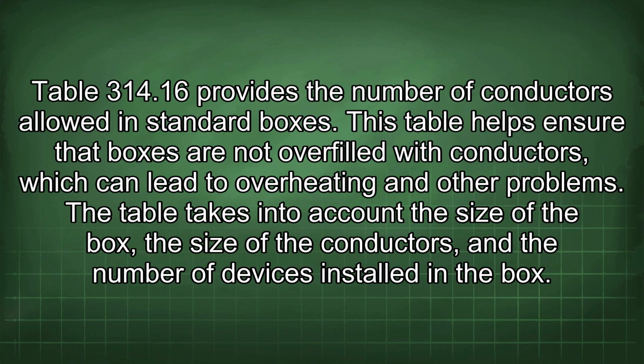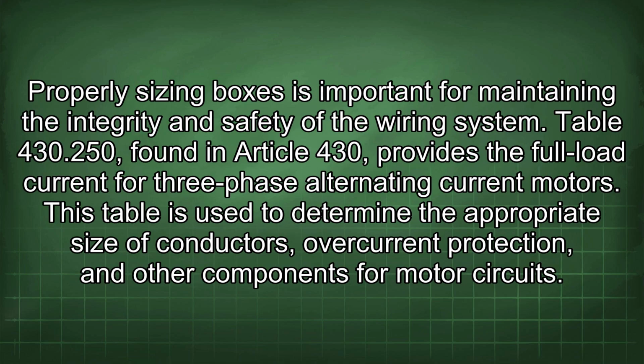Table 314.16 provides the number of conductors allowed in standard boxes. This table helps ensure that boxes are not overfilled with conductors, which can lead to overheating and other problems. The table takes into account the size of the box, the size of the conductors, and the number of devices installed in the box. Properly sizing boxes is important for maintaining the integrity and safety of the wiring system.